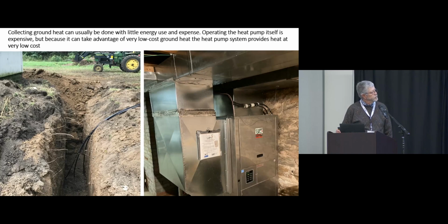If you didn't have the geothermal lines in there and just operated the heat pump, you wouldn't get any more than you would having toasters or hair dryers there. The beauty of the heat pump is that refrigeration cycle that can take advantage of the geothermal lines.